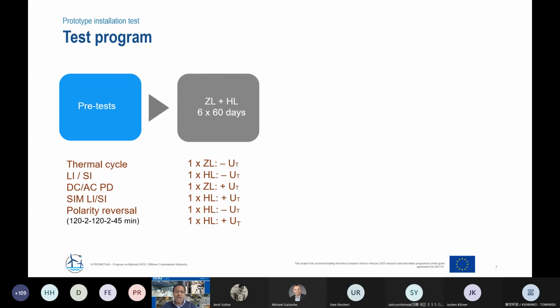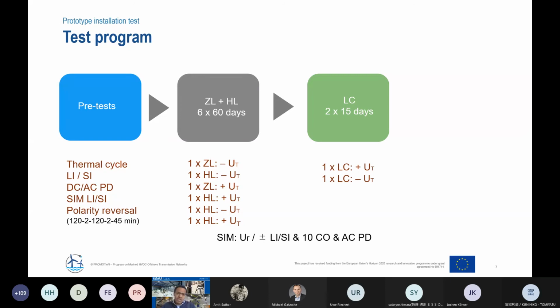And then, of course, we change polarity at each testing block. So one testing block at positive polarity for 60 days, and then we reverse at different loading. In between each testing block, of course, we apply superimposed impulses, both lightning and switching, and also close-open operations of the disconnectors and earthing switch. And AC partial discharge measurements are performed to monitor the condition. And this, as you see, takes the 1 full year for just the long-term test, and that is followed by a load cycle.